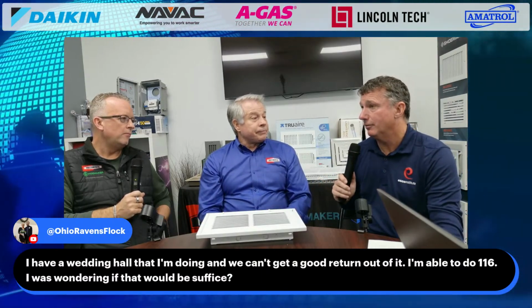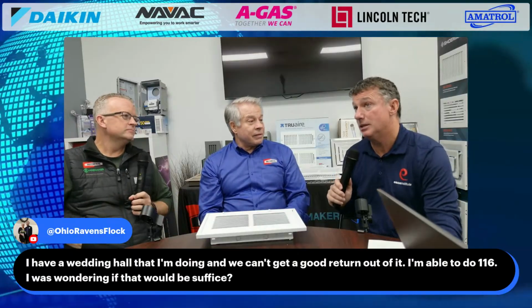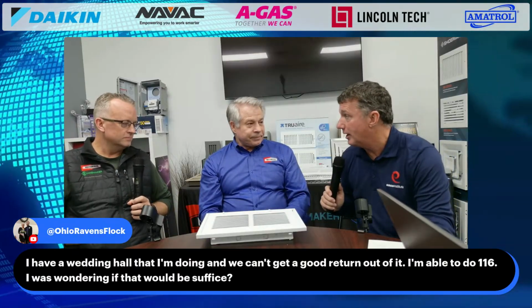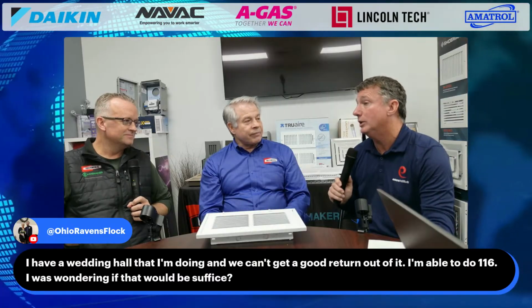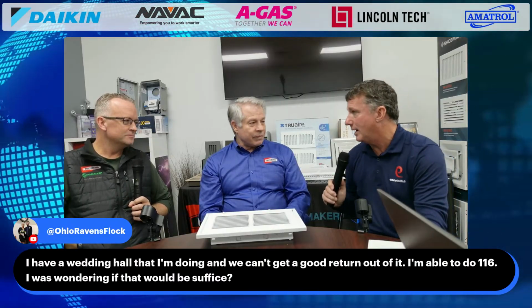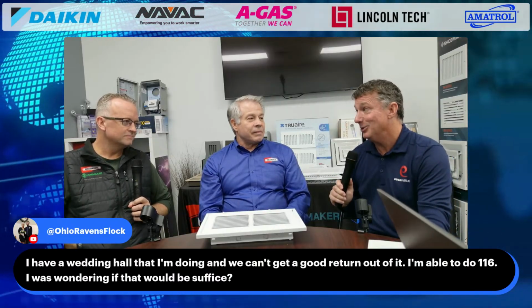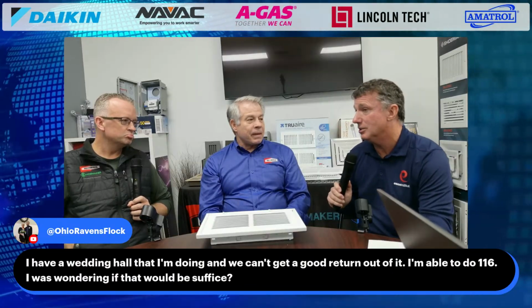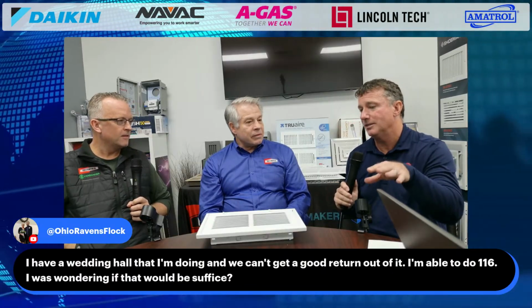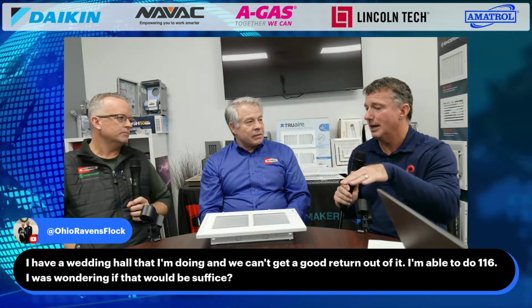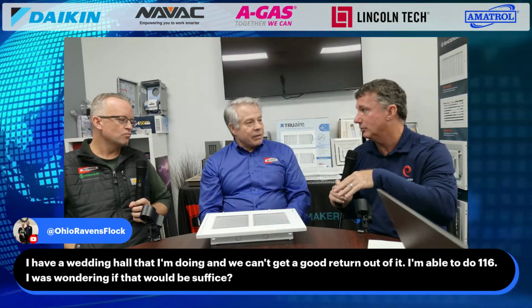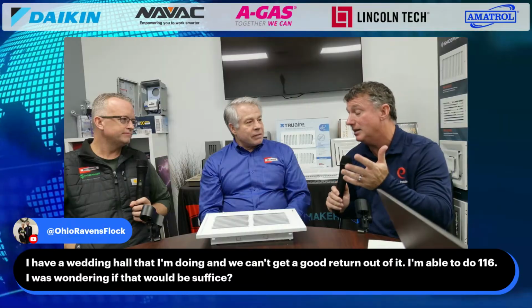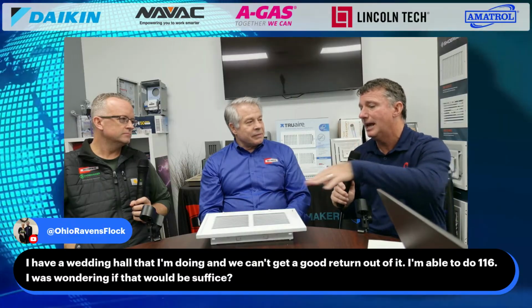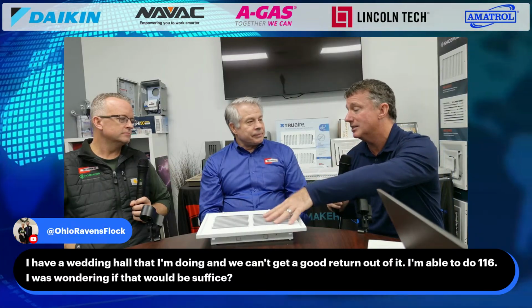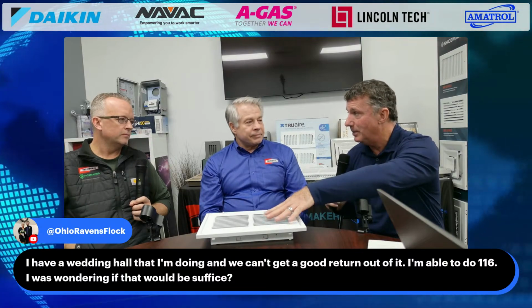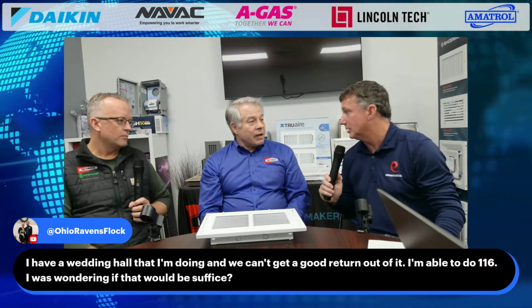Make sure you're within that NC rating for that application. Yeah, because if we're designing it for a residential application, or say we've been a residential technician all of our life, this is how we've learned, and all of a sudden we get into a new requirement, it is going to come down to noise level. We have to understand what specification is changing so that I make sure that I'm using the right calculations for it. I mean, it could be a matter of understanding how the air is being returned and supplied into that space, and making the proper grill register selections could change things.